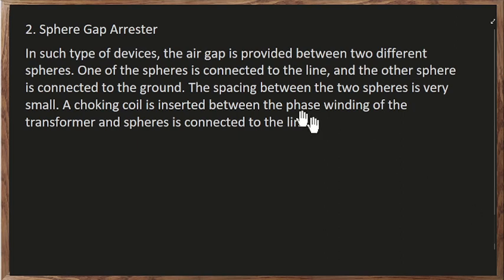Then we have the sphere gap. In such type of devices, the air gap is provided between two different spheres, kaya siya sphere gap. One of the spheres is connected to the line and the other sphere is connected to the ground. So the spacing between the two spheres is very small. A choking coil is inserted between the phase winding of the transformer and the sphere that is connected to the line.